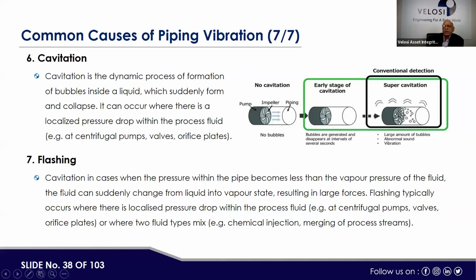Flashing, I mentioned earlier, is a more common phenomenon in condensate, especially steam condensate when it is being separated out, either by steam traps or for some other reasons. Normally, when high pressure steam condensate is separated and goes to a low pressure area or the deaerator area, in that scenario steam can flash and it can cause high erosion, corrosion, noise and vibration. Those areas are properly covered by appropriate design. Sudden pressure changes should be avoided, so that flashing of the condensate back to steam can be avoided. Sometimes flashing is also a problem when we have chemical injections or merging of process streams in various phases.